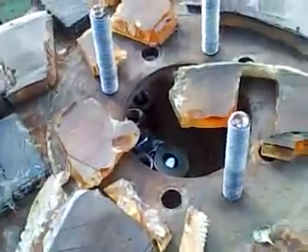All right, hey guys. This is my thousand-watt wind turbine — a catastrophic failure. As you can see, this is one of the rotors. Magnets separated, and we found them all over the field along the radial line of the rotational axis.